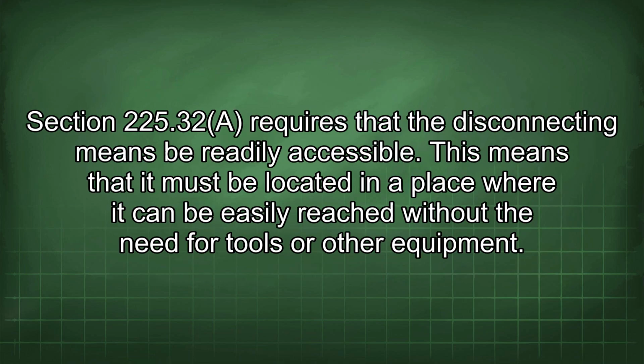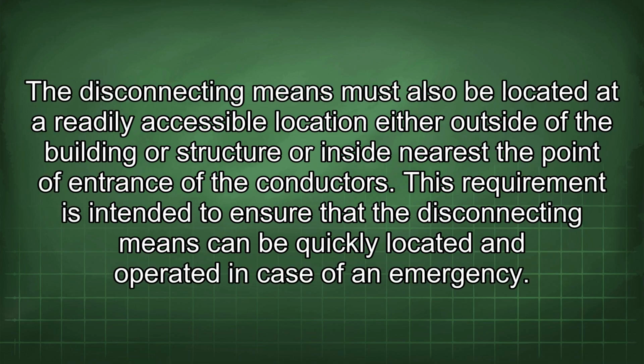Section 225.32 requires that the disconnecting means be readily accessible. This means that it must be located in a place where it can be easily reached without the need for tools or other equipment. The disconnecting means must also be located at a readily accessible location either outside of the building or structure or inside nearest the point of entrance of the conductors. This requirement is intended to ensure that the disconnecting means can be quickly located and operated in case of an emergency.